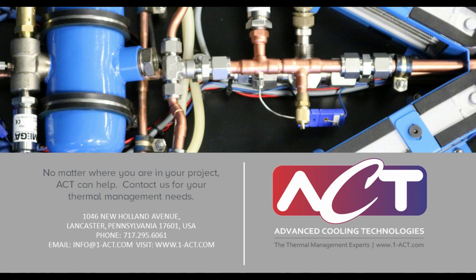Thank you. Is having an accumulator necessary in P2P systems? It is. The accumulator in a pumped two-phase system serves a very valuable purpose. Because we have transition from liquid to vapor, and vapor is often several orders of magnitude less dense than liquid is, we need a place for that volume expansion to occur. And that's what the accumulator does in a two-phase system. As we transition from liquid to vapor, we're decreasing the effective density of our system, which means we need more volume. So if we didn't have a place for that less dense vapor-liquid mixture to go, the system pressure would start to climb, and it would potentially risk safety in the system. So the accumulator is absolutely necessary in a pumped two-phase system.